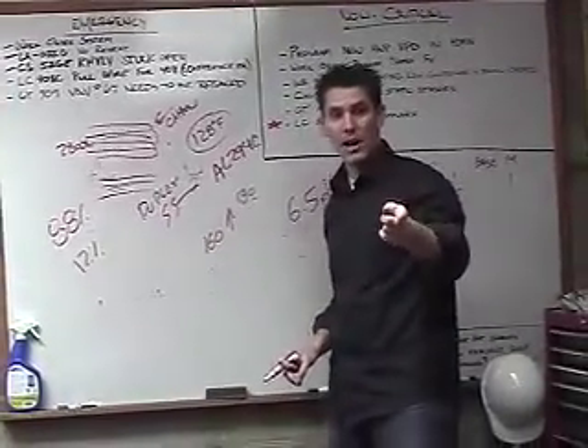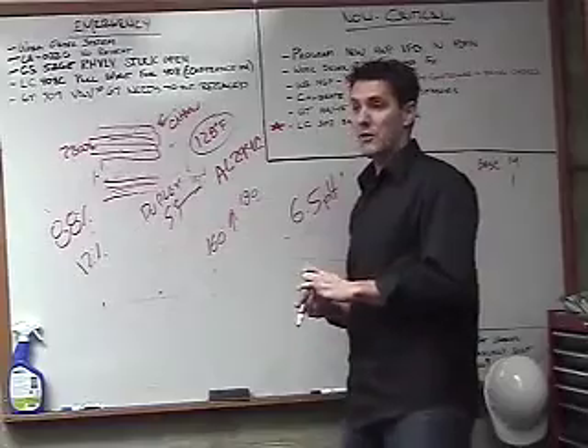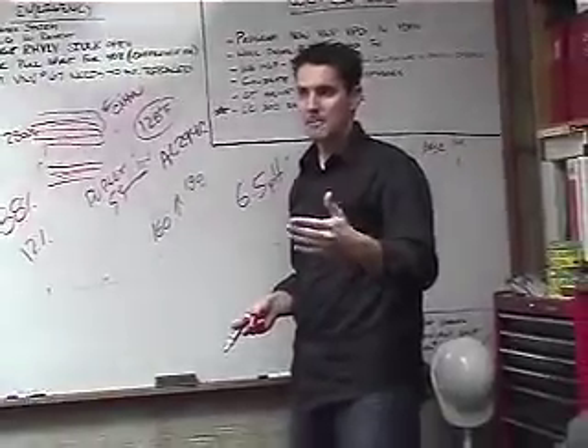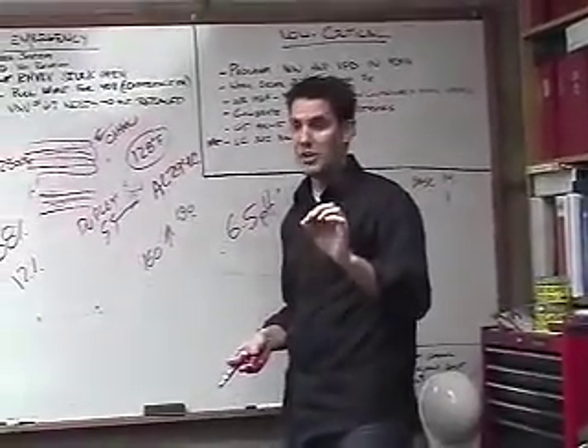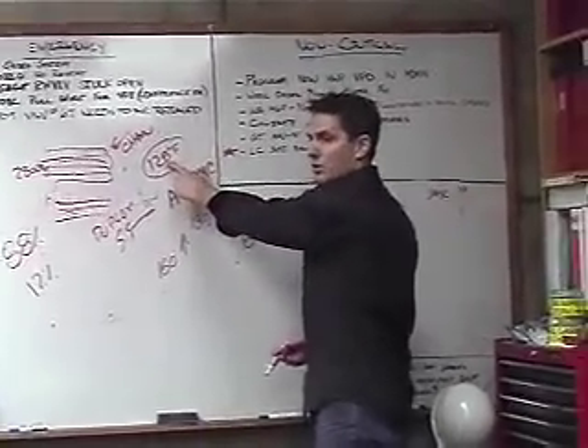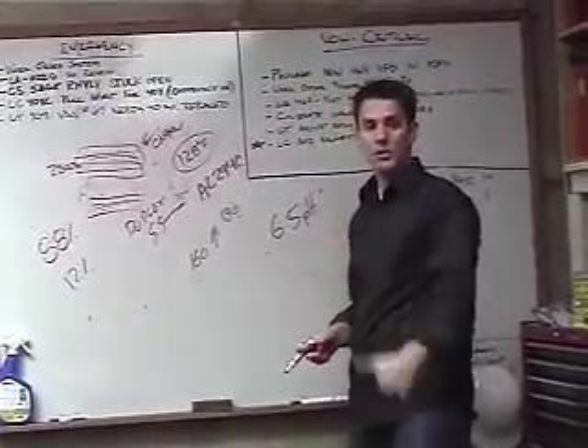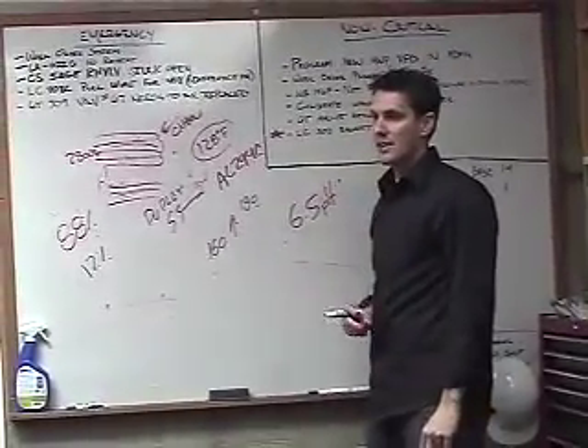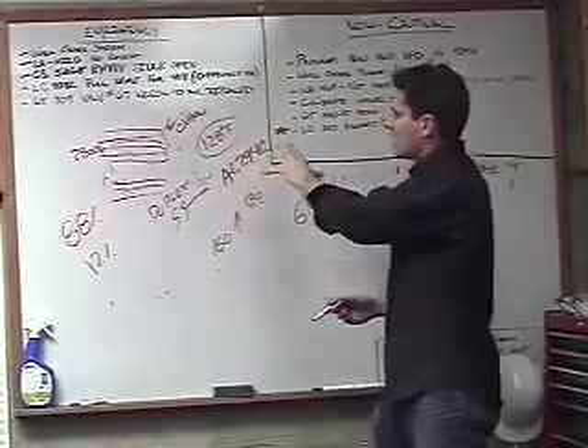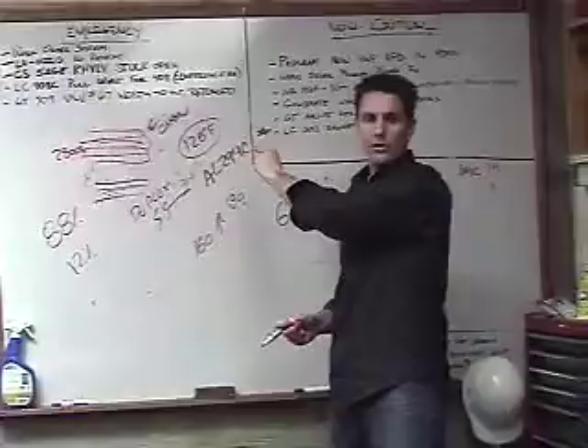128. Less than 128. That's why these boilers that you've got, I bet if you go back and read their warranty, they state if you operate our boiler less than what temperature? Anybody know? 160. It's actually 140. With these boilers, if you bring back colder water than 140, you violate their warranty. They're trying to give you a buffer, a pillow, a cushion so that you don't ever hit this, because you will kill those boilers. You will rot out all those tubes from the outside from all of that acid. So again, they're trying to prevent that. So our goal is to get our water to come back to these boilers colder than 128 degrees. If you don't, you wasted your money on a condensing boiler.